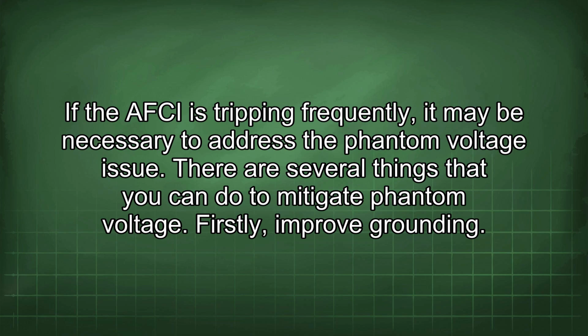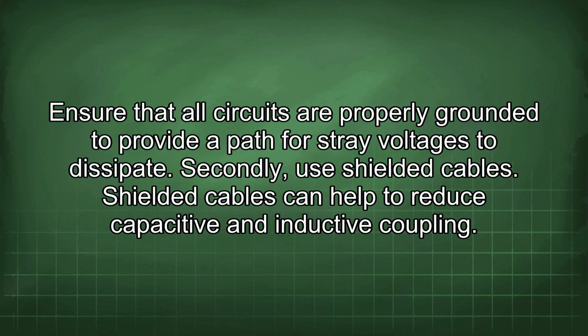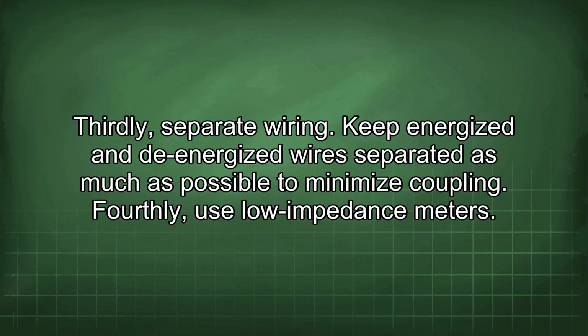There are several things that you can do to mitigate phantom voltage. Firstly, improve grounding. Ensure that all circuits are properly grounded to provide a path for stray voltages to dissipate. Secondly, use shielded cables. Shielded cables can help to reduce capacitive and inductive coupling. Thirdly, separate wiring. Keep energized and de-energized wires separated as much as possible to minimize coupling.